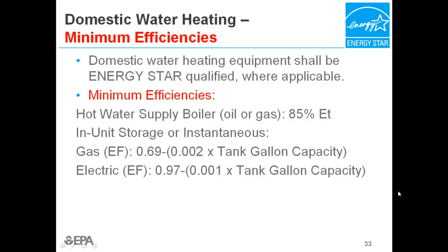For hot water boilers, gas or oil fired, in-unit or central, the minimum efficiency allowed in the prescriptive path is 85% thermal efficiency. For in-unit tankless or storage water heaters, these equations determine the minimum efficiency. For example, a 50-gallon gas storage water heater must have an energy factor of at least 0.59. Since storage water heaters are readily available as Energy Star qualified, this minimum will generally be exceeded due to the higher criteria for Energy Star qualified water heaters. To determine minimum efficiencies for tankless systems, use 1 gallon for tank gallon capacity.